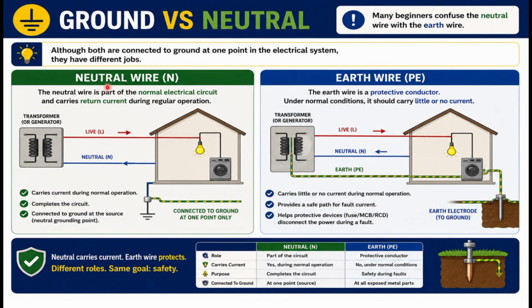The neutral wire is part of the normal electric circuit. It carries the return current. Live current goes into the lamp, it flows through the device and comes back through the neutral wire. So that is the normal procedure. And this is the earth connector connected to the ground at only one point. So neutral carries current during normal operation, completes the circuit, and is connected to the ground at the source. That is all for the neutral wire.